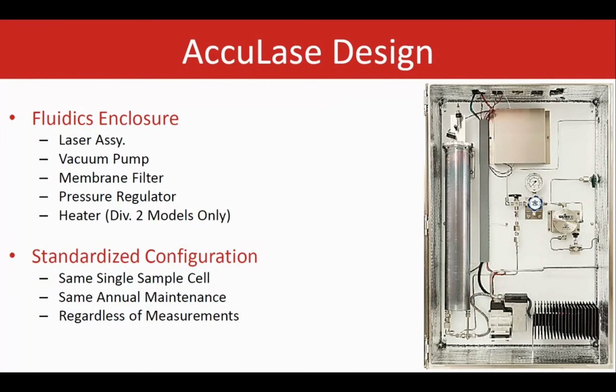This one here shows the laser assembly, cell, heater, vacuum pumps, as well as the components for the sample conditioning system, such as the membrane filter and the pressure regulator. The design is really space-saving. It's simple and robust and to the point. Again, only one single sample cell for all of those analyses. And it's important to emphasize that because that's the differentiator in the market for this analyzer for a variety of applications. Also, the same maintenance requirements are used for all of the units and models. So that makes it easy to catch up for those who are worried about the maintenance side.